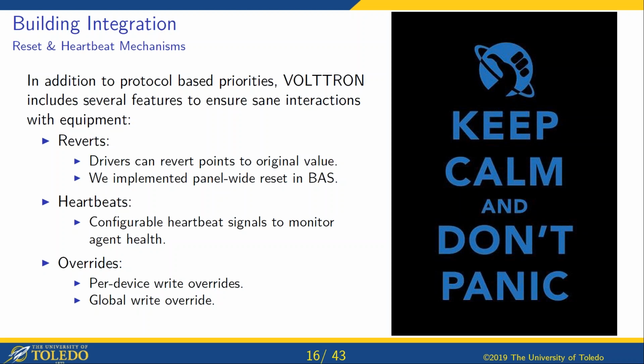So we protected the occupants first so that things don't get out of control, even though we're applying this as an energy reduction resource. Right, and we also do have controls in place when we're actually running algorithms to make sure they're not changing set points more than usually about 2 degrees in either direction. And rarely do they actually reach the limits of that for anything that we're trying to do. And we're usually not looking to see a difference in the actual temperature that things are keeping. We're actually looking to see if there's not a difference, typically.